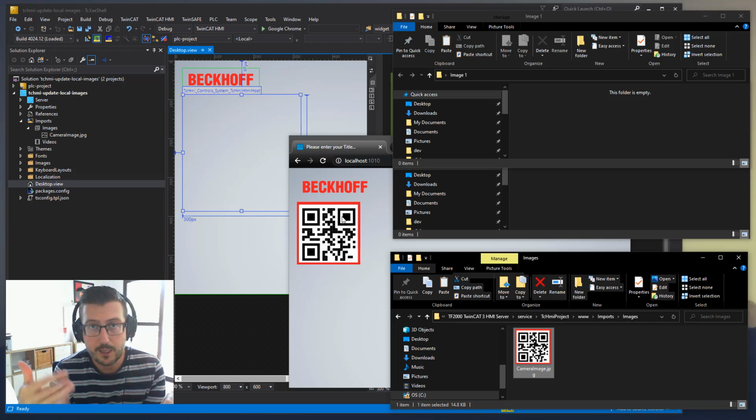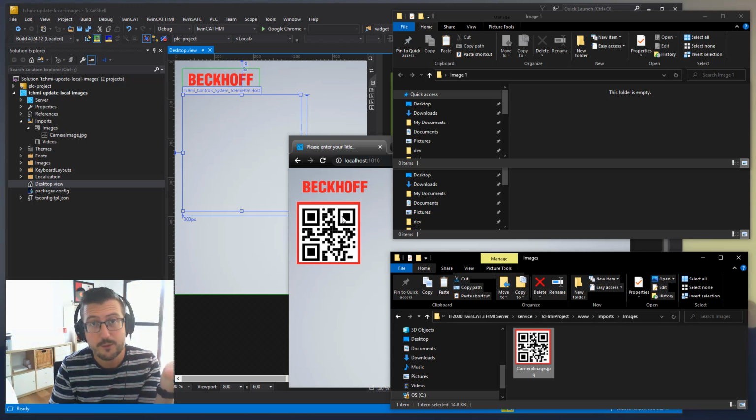That's worthwhile enabling, because if you enable the Unified Write Filter on a portion of your drive, maybe all of your drive, obviously you've got to exclude your project files that you need to allow changes to. But if you hit a folder and say no, don't allow writes to occur in this folder, what that write filter will do is actually store it to memory. I believe it just does store to memory. You wouldn't want to store it to hard drive, otherwise that negates the whole process. But yeah, tell it to store it to memory instead.